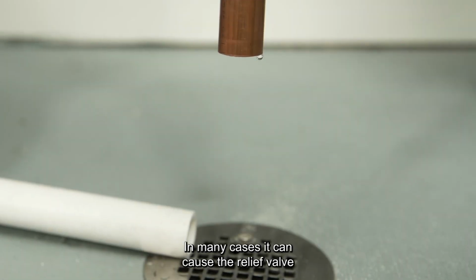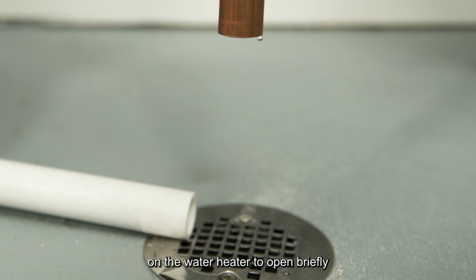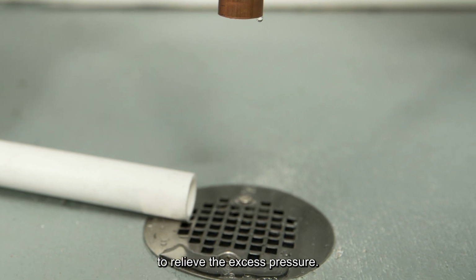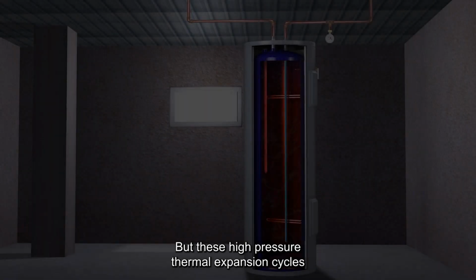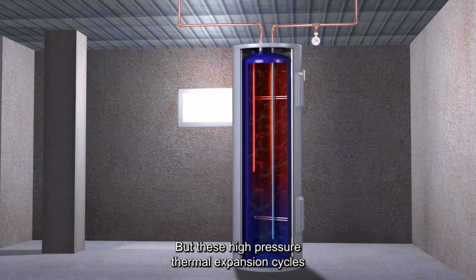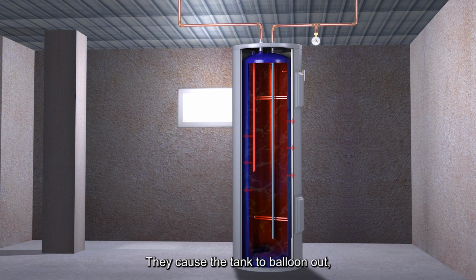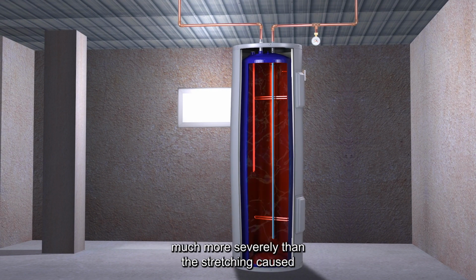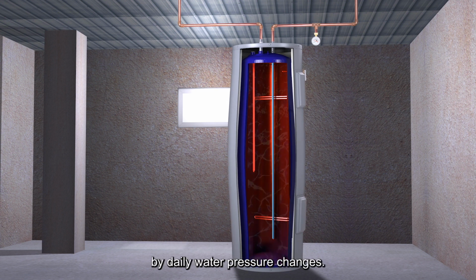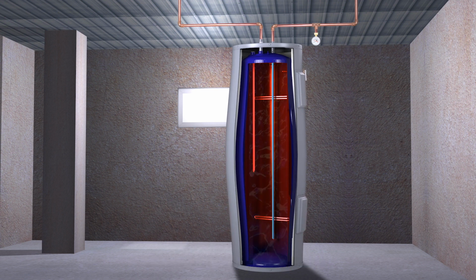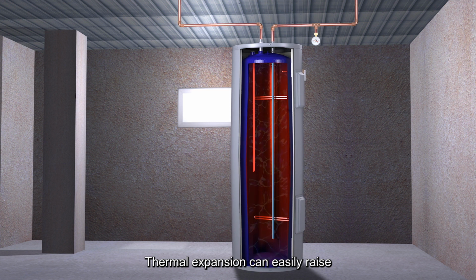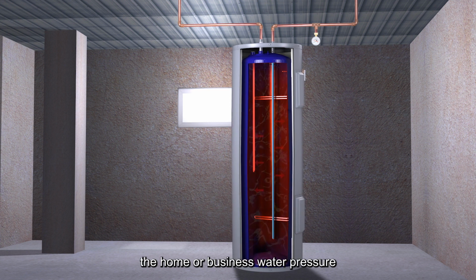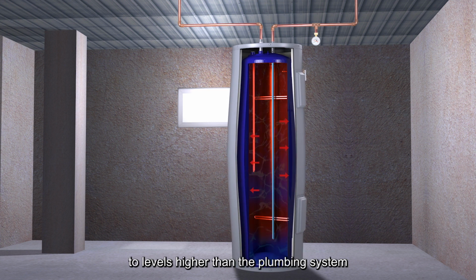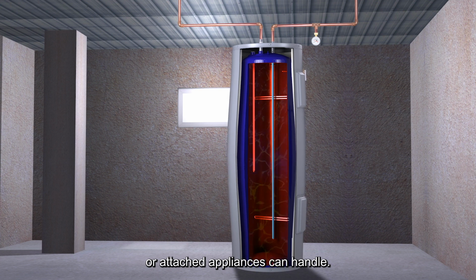In many cases, it can cause the relief valve on the water heater to open briefly to relieve the excess pressure. But these high-pressure thermal expansion cycles do something else. They cause the tank to balloon out, much more severely than the stretching caused by daily water pressure changes. Thermal expansion can easily raise the home or business water pressure to levels higher than the plumbing system or attached appliances can handle.